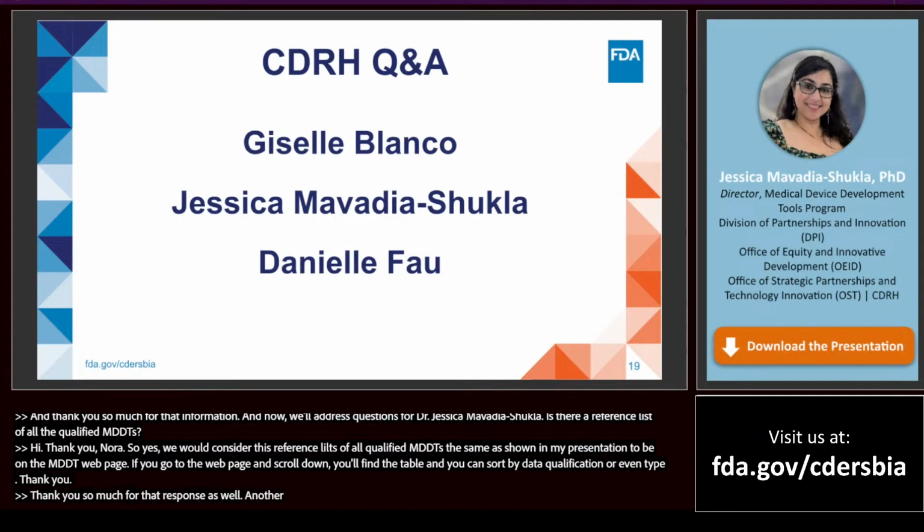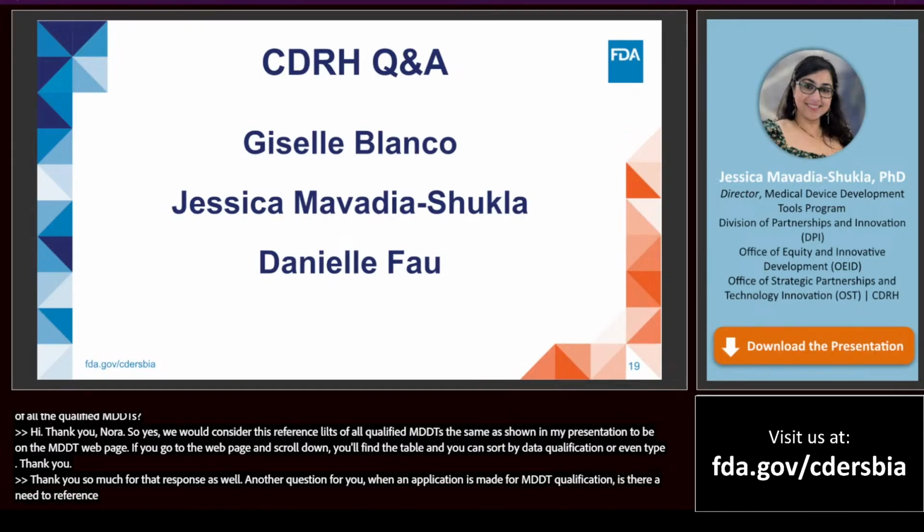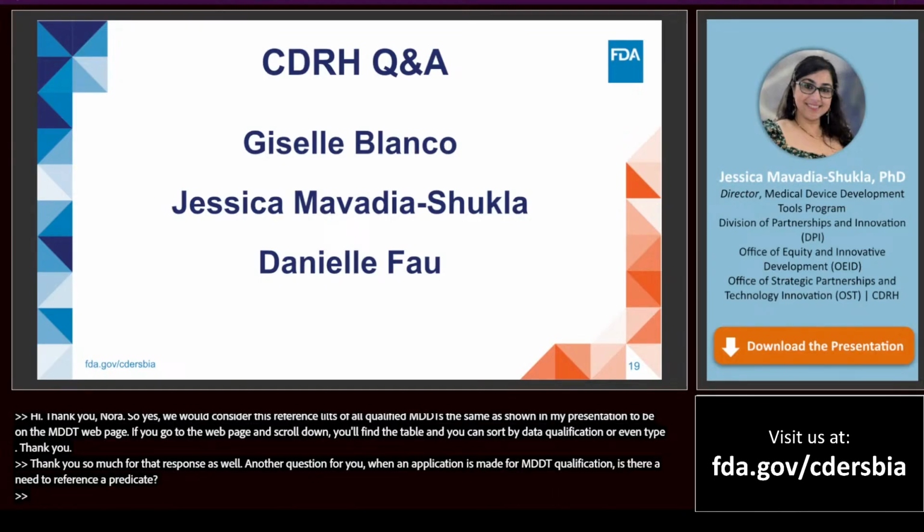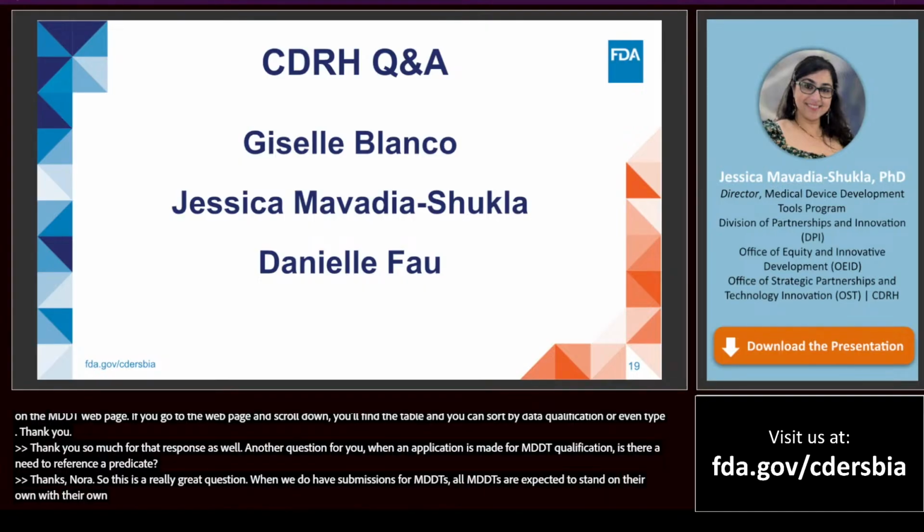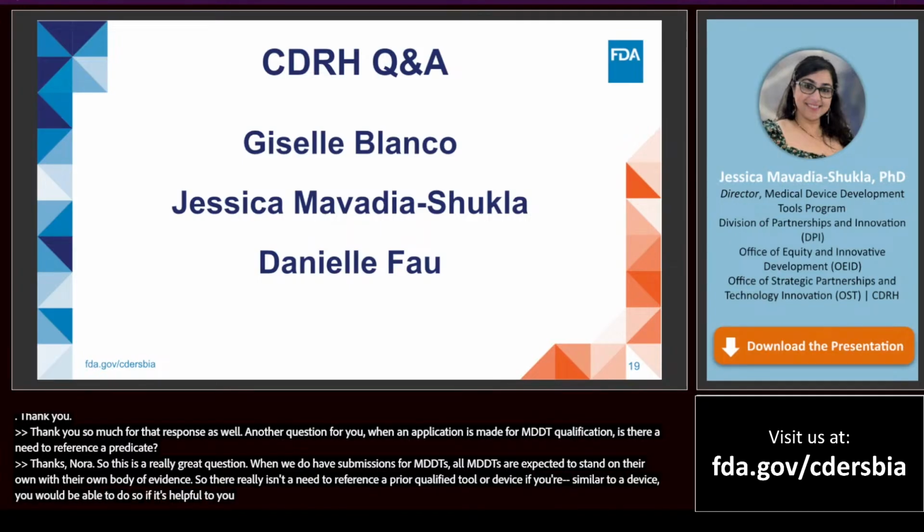Another question for you. When an application is made for MDDT qualification, is there a need to reference a predicate? Thanks, Nora. This is a really great question. When we do have submissions for MDDTs, all MDDTs are expected to stand on their own with their own body of evidence. So there really isn't a need to reference a prior qualified tool or a device. If your function is similar to a device, you would be able to do so if it's helpful to you, but certainly this is not necessary.